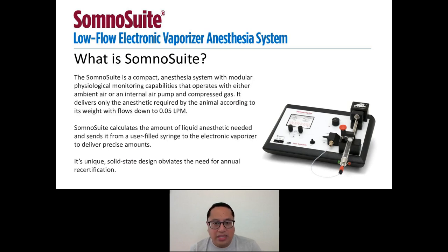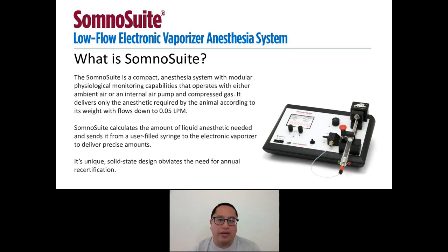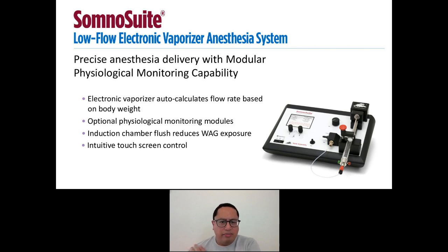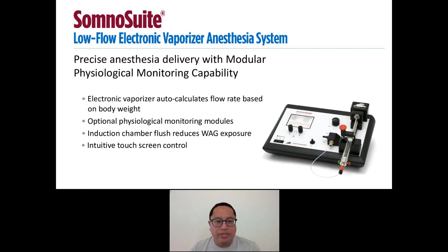The integrated electronic vaporizer can use either ambient air or compressed gas to deliver anesthesia based on the animal's weight. Because of the low flow rate of the system, you can save on the amount of anesthetic and compressed gas used over time. Since small amounts of anesthetic are being used, waste gas exposure is reduced for the users. All SomnoSuites are equipped with the RightTemp module, which is a temperature monitoring and homeothermic control that uses far infrared warming.